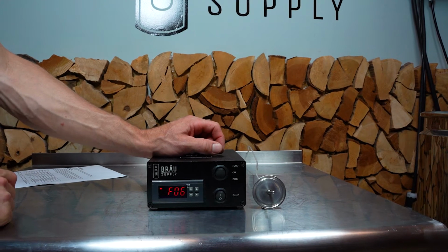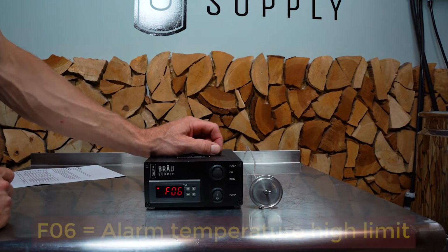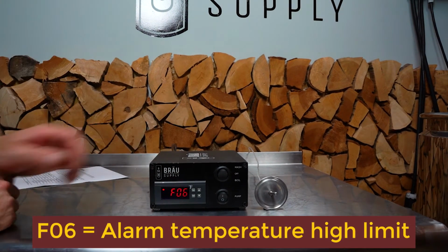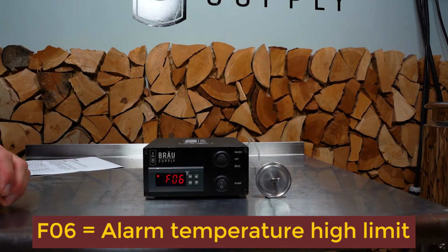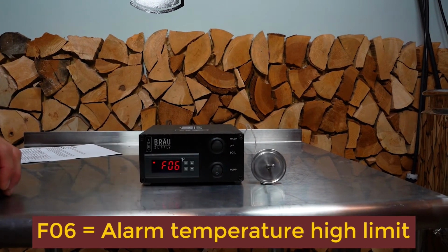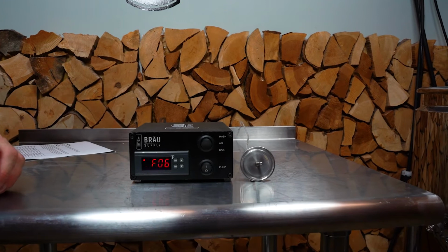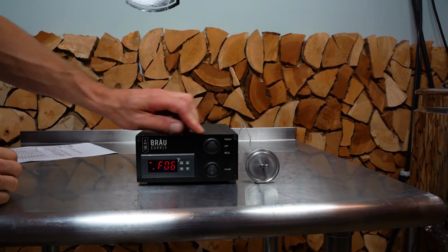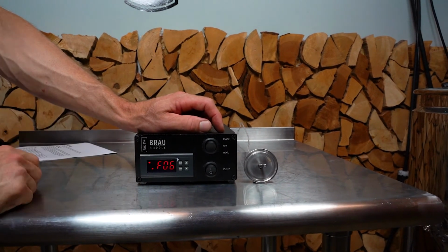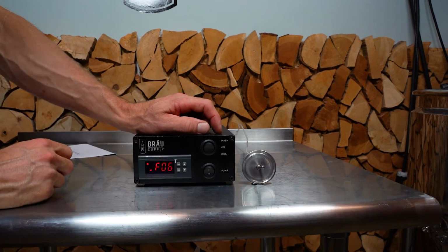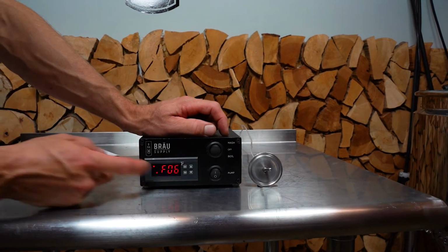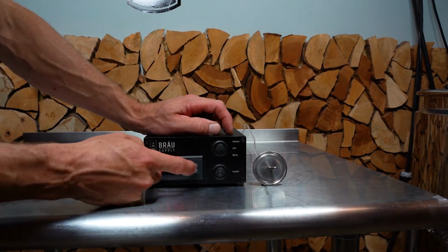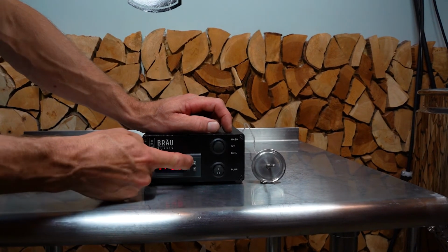F06 is alarm temperature high limit. And so this is your alarm, your high limit temperature. So it's set to 206 degrees. Sometimes people want to know why it's beeping at 206 degrees. This is why. And every time it drops below 206 and it comes back up to 206, it will beep again. And so if you don't want it to beep as it's approaching boil, you can change that.